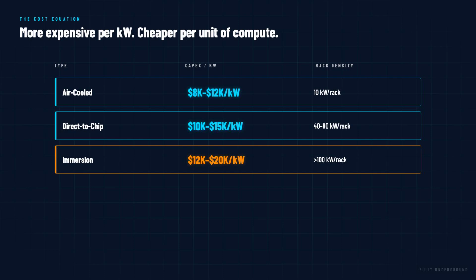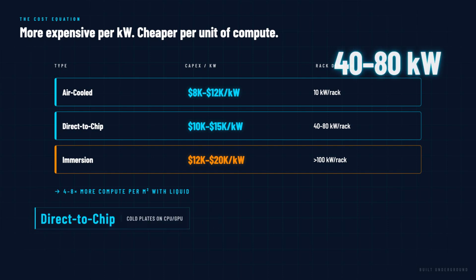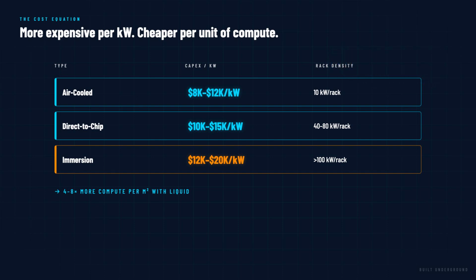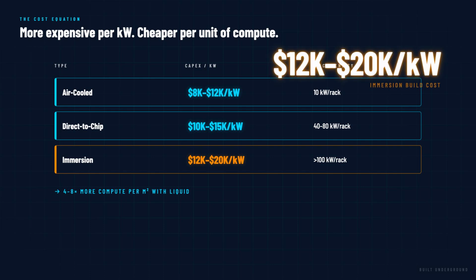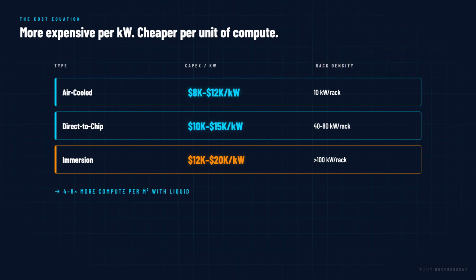Here is where it gets practical. A traditional air-cooled data center at 10 kilowatts per rack costs roughly $8,000 to $12,000 per kilowatt of IT capacity to build, including all cooling infrastructure. Direct-to-chip liquid cooling at 40 to 80 kilowatts per rack costs roughly $10,000 to $15,000 per kilowatt to build. Higher capital cost, but you fit 4 to 8 times more compute into the same floor space. Immersion cooling at 80 to 150 kilowatts per rack costs roughly $12,000 to $20,000 per kilowatt. The highest capital cost, but the highest density and the lowest operating cost per kilowatt once running.